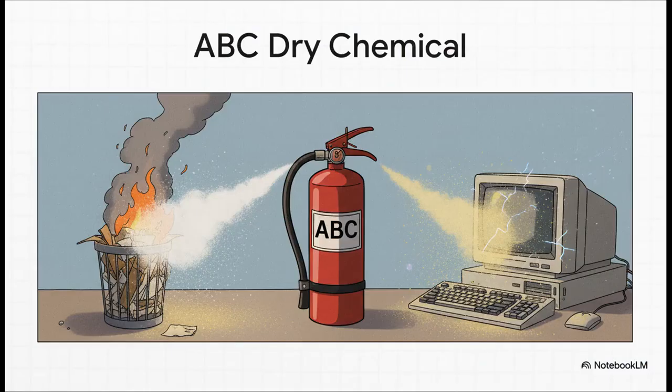So that ABC dry chemical, it's your jack of all trades. It's affordable, it's common, and it's effective on the three most common fire classes. But, and this is a big but, it leaves behind this fine, corrosive powder that will absolutely destroy electronics. So for the ARE, think of this as your default choice for a typical office space, but be very careful where else you specify it.